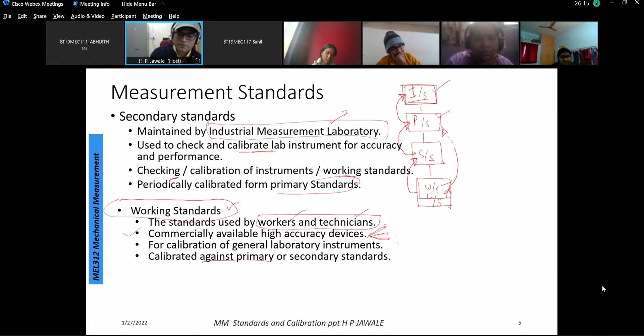So for calibration of general laboratory instruments, we use the working standards, or directly we use them for measuring the workpiece. It is compared against the primary or the secondary standard. Mostly it is compared with the secondary standard, but sometimes it can also be compared with the primary standard, which is placed at some national laboratory, right?